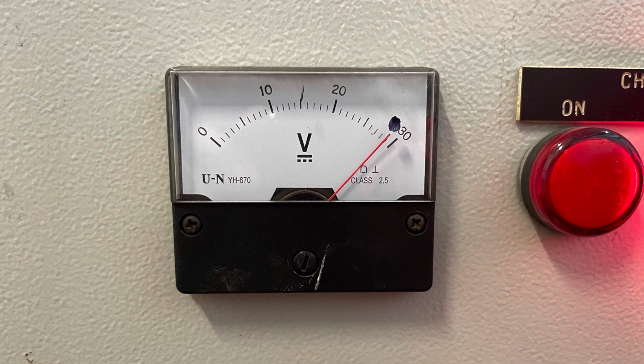Anything that goes below 15 could cause the whole system relay to malfunction and the contactor to release. Thus, the system will reset by itself. Under auto mode, it won't be able to start automatically, unless you try manual. Here I have a video using manual mode, and it was successfully able to crank.